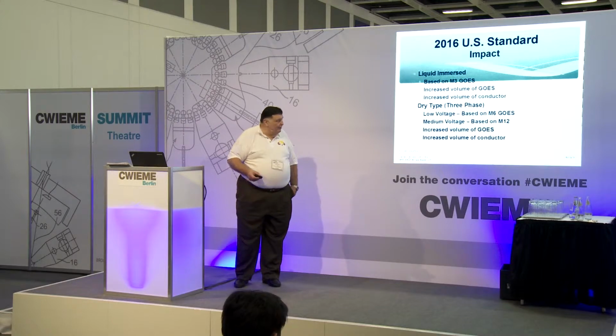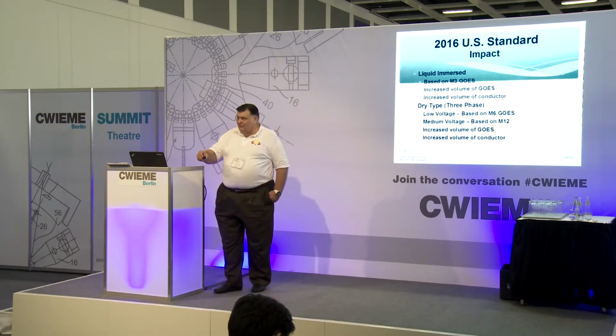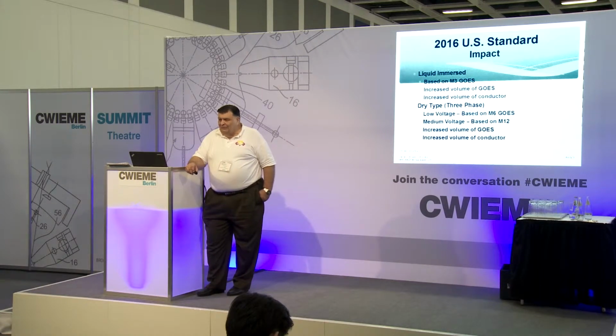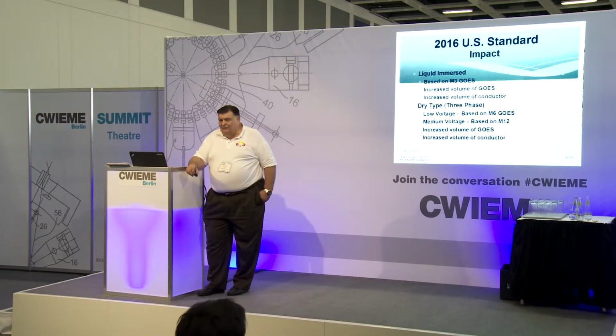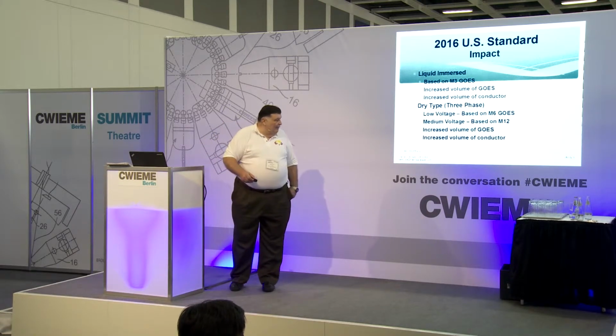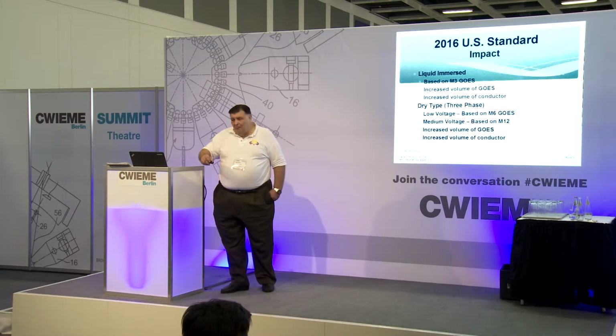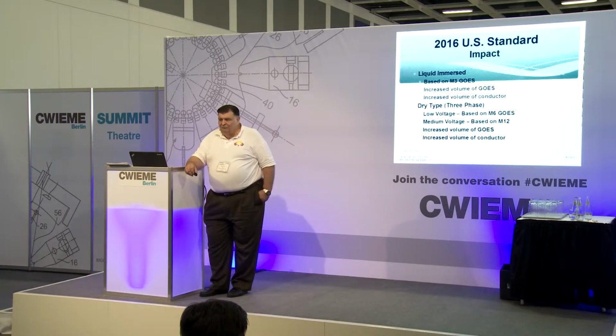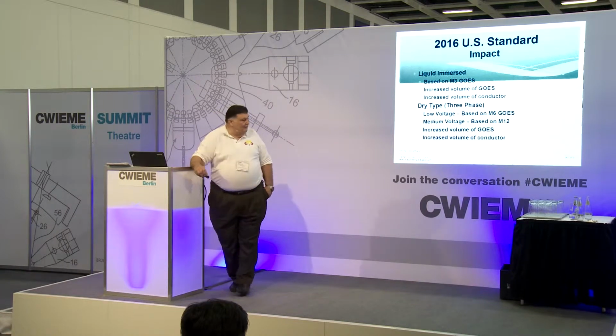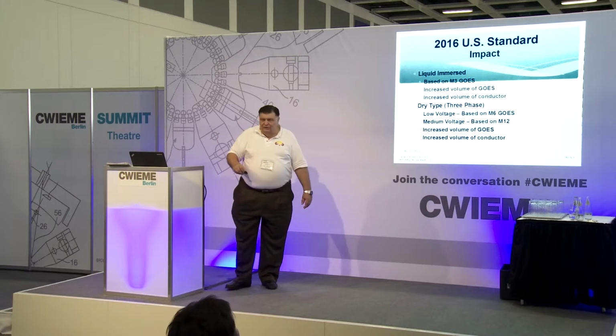Dry type, three-phase: M6 becomes the base for grain-oriented. Today, on the dry types, even the three-phase, an M12 or an M15 is the common material. With the new standard, that's going to be M6. And the increase in volume: core weight increases 20 to 25% in core mass, and there is a 25% increase in the amount of conductor. So you're going to see dramatic increases in size. The medium voltage can still use an M12 as a base.